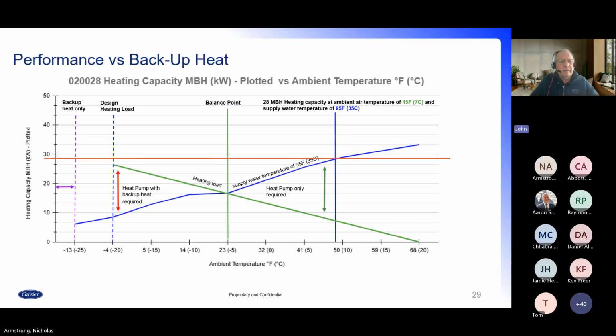So our backup heat would be using heat from 23 degrees down to -4 Fahrenheit. Of course, there's a point in time where the heat pump just cannot extract any more temperature out of the air, and that's going to be at -13 Fahrenheit. At that point, backup heat only is what you're going to use. So again, this chart is representative of a 95-degree Fahrenheit fluid temperature with a 45-degree outside air temperature. Okay, next slide.